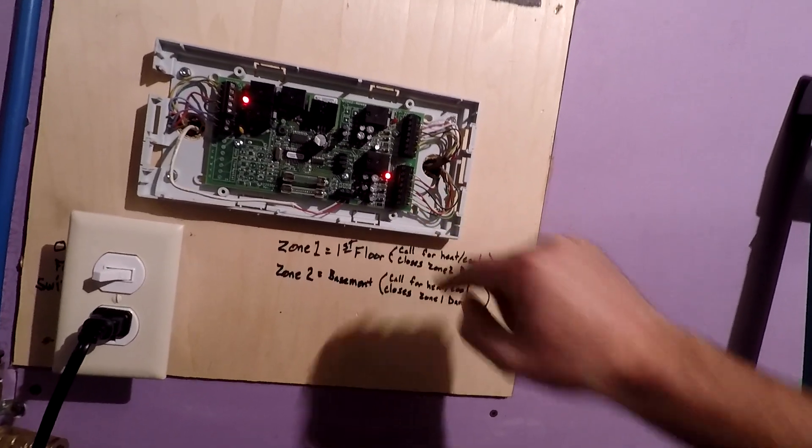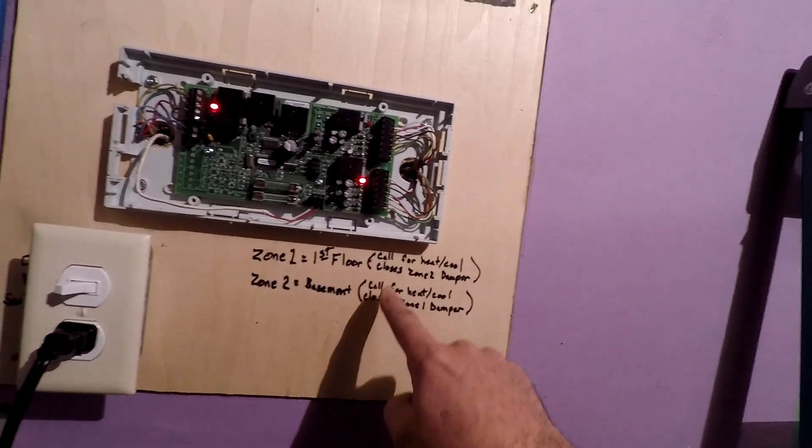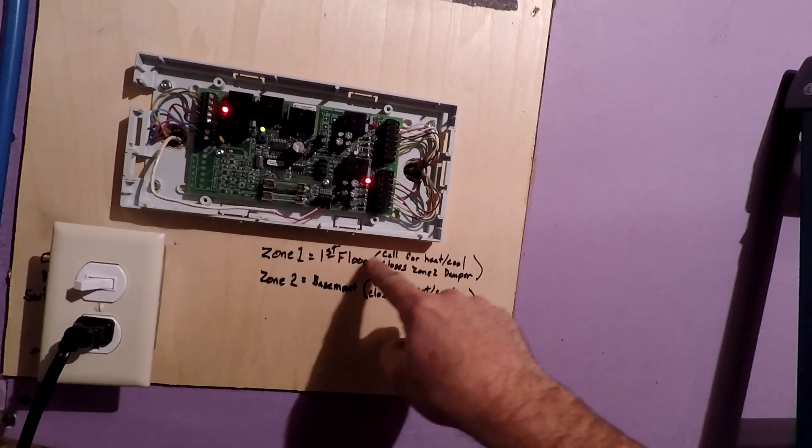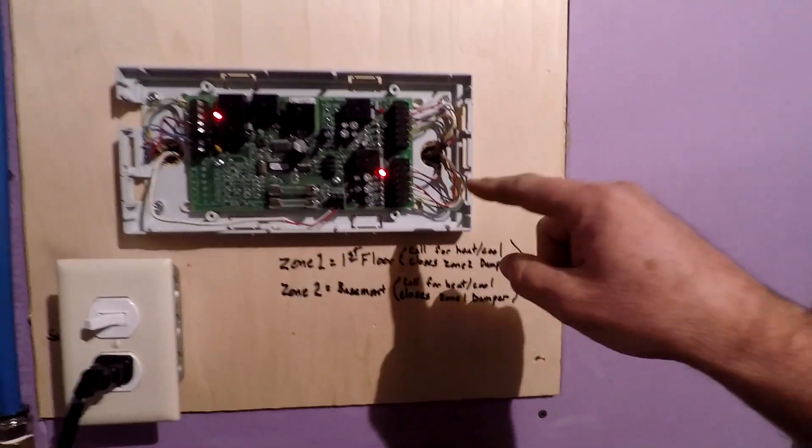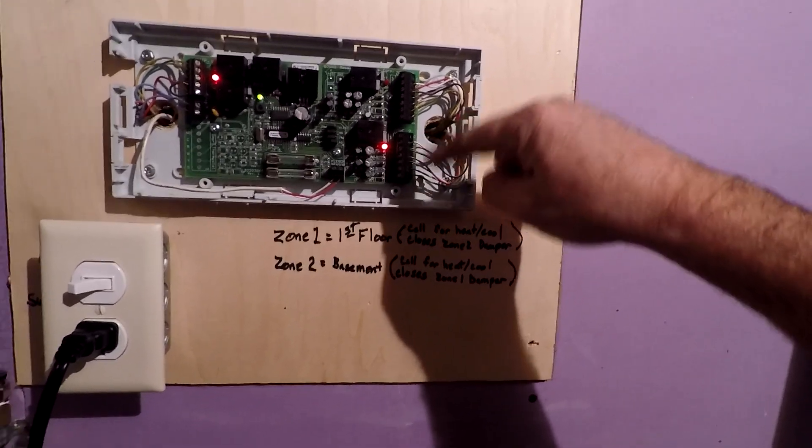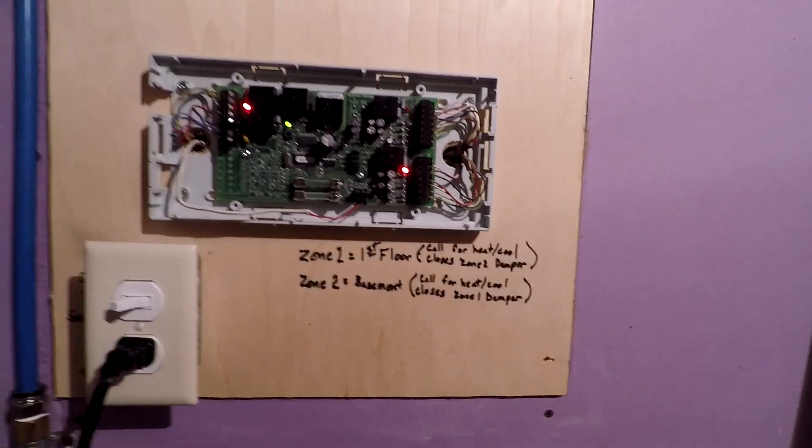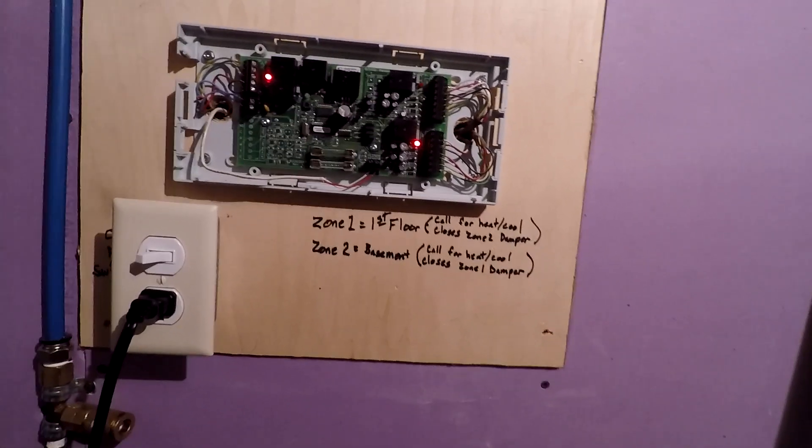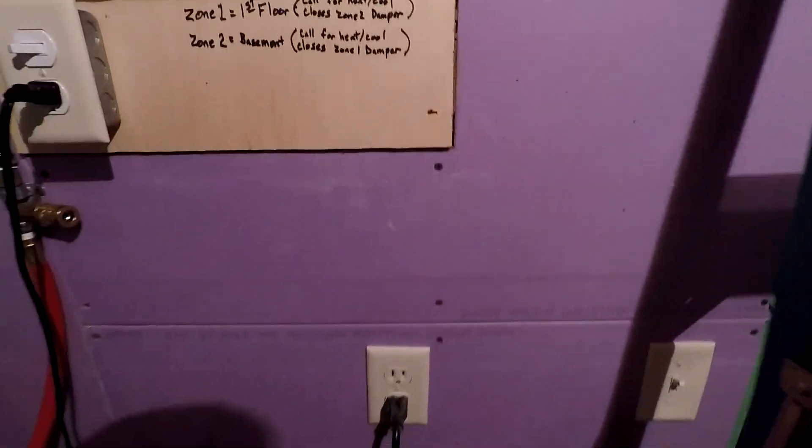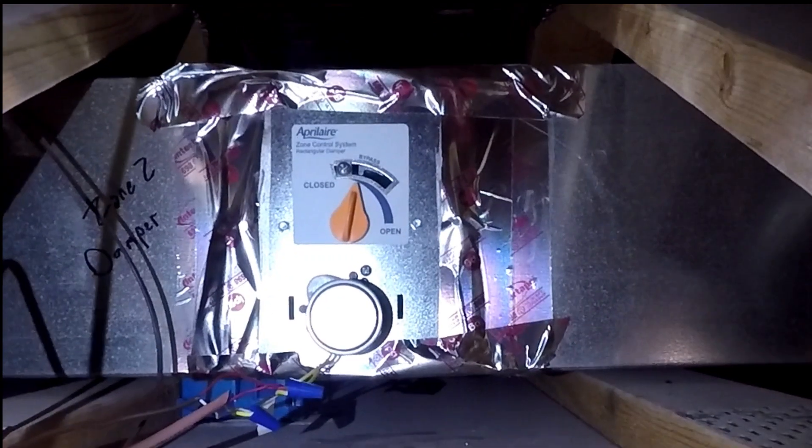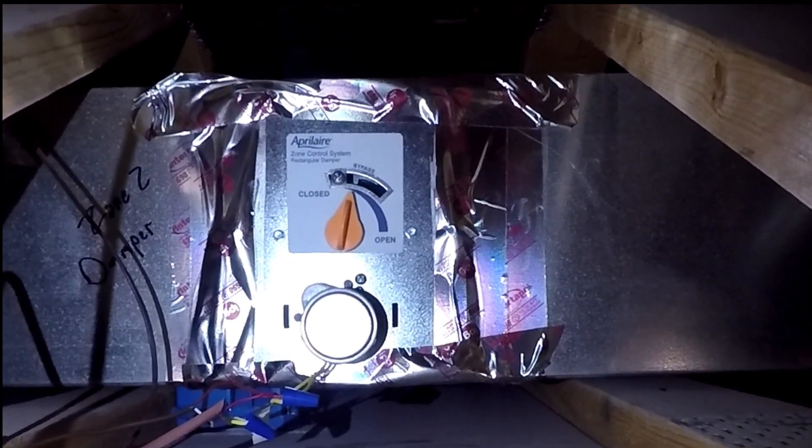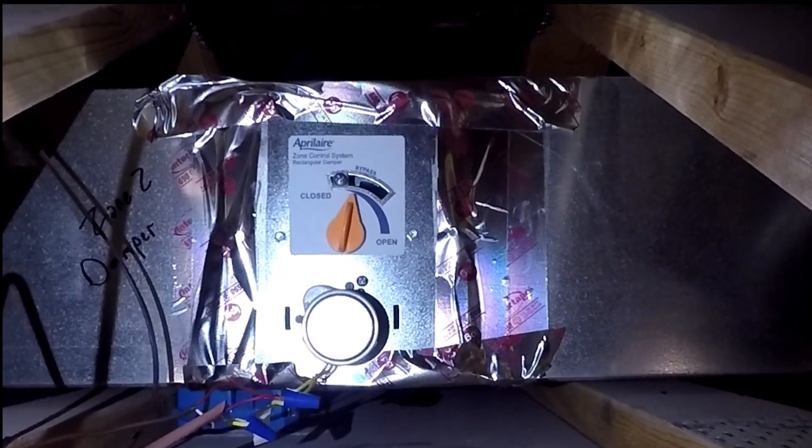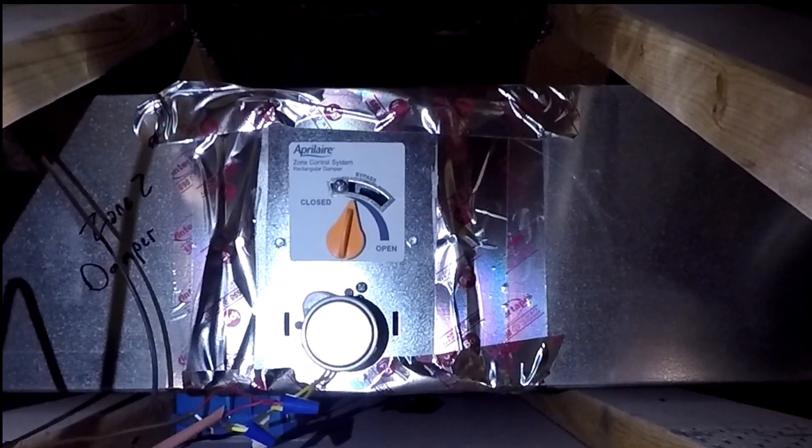This bank of wires here is my zone two bank. Zone one is calling for heat and it's closing zone two damper. There's 24 volts of power coming from this block and going to the zone two damper, and that's supposed to close the dampers. The dampers are normally open if there's no power at all. That's working correctly in this particular zone. And that damper is right there.